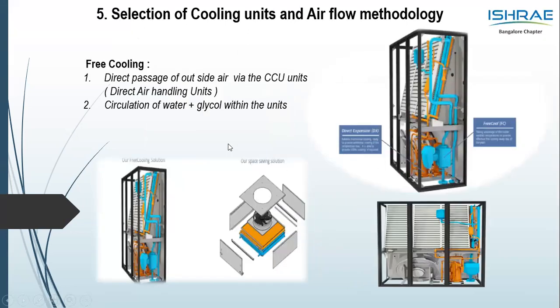So on the next slide is the free cooling. We saw on the traditional standard, the CCU units, which goes into the server room. Again, the concept of free cooling. What is free cooling? When again referring to the ASHRAE 18/27, when the outside ambient is close to 27, why don't we get the outside ambient into the server room rather than running the CCU unit, which has chiller, which has compressor, fans, and a lot of mechanical components which draw a huge amount of power.